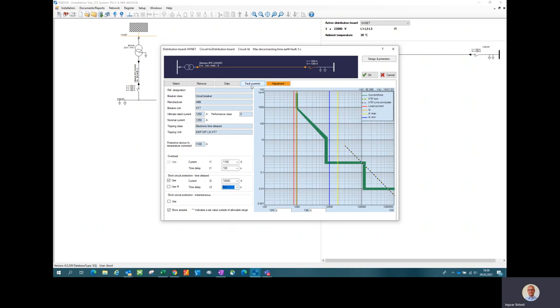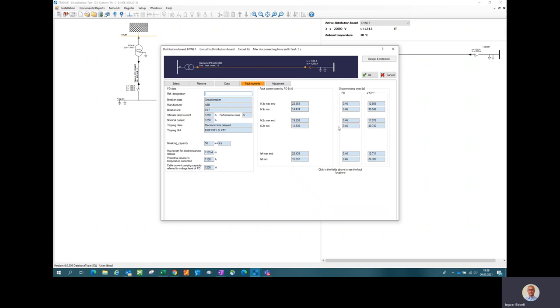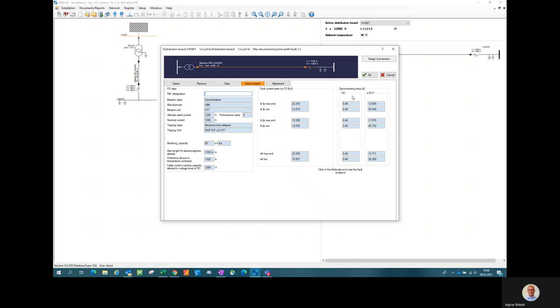It will make it easier to achieve the selectivity throughout the system. The time delay here, you can choose 0.4 seconds. There should not be any problems, we can have a check of the fault currents, looks great. If we choose the value of these settings that's outside of what's recommended, if you can get disconnection times that's longer than what the cable can handle, these fields will be red.